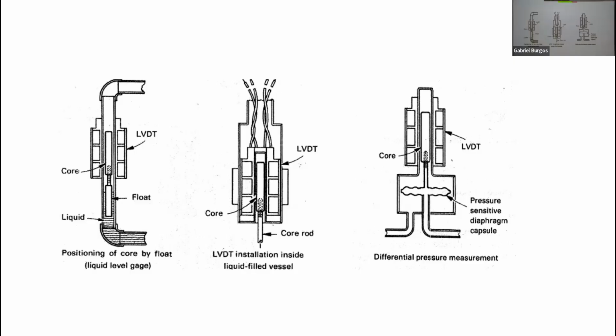One place LVDTs are commonly used is in two-stage servo valves, where you have a pilot valve and a main spool. You want to know what the main spool position is to give feedback to the pilot. Again, you have to do an integration, but the end result is you can use this. Here's an example of one where you have a float inside hooked up to the core, and it can measure liquid level, as a point of interest.